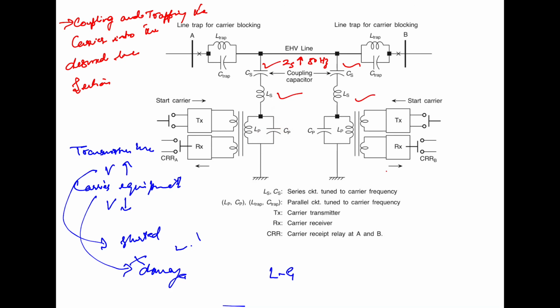which is tuned to the carrier frequency. Now the coupling capacitor drops most of the 50 hertz voltage, so that a very small 50 hertz voltage appears across the signaling equipment. The series circuit, that is CS and LS, is designed to resonate at the carrier frequency. Since the impedance Zs of the series circuit is ideally zero, it provides a very good coupling at the carrier frequency.